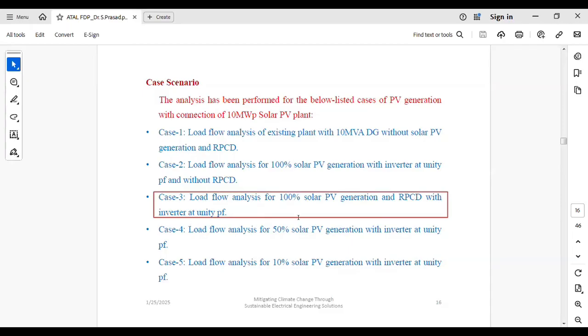This is the case study I have considered, and based upon it I will show you the ETAP simulation results. Basically, we need to perform all these case studies if you are going for load flow analysis of a PV plant connected to the grid. You have to go for 100% generation at unity power factor, 50% generation at unity power factor, and 20% generation at unity power factor. These are the different case studies, and you have to observe the behavior of the plant when it is integrated to the grid.